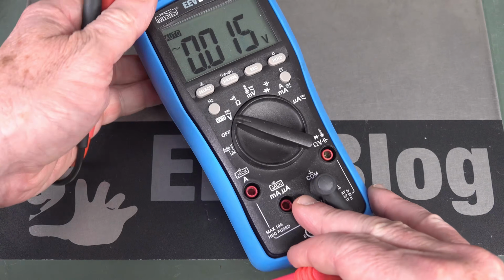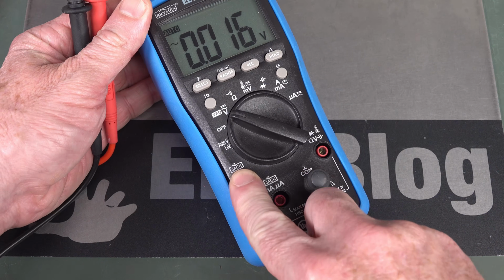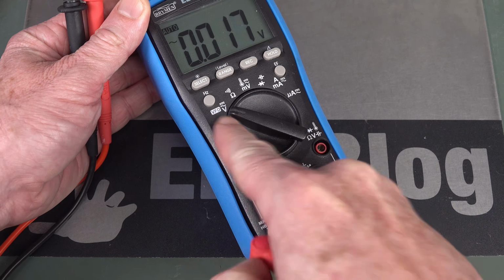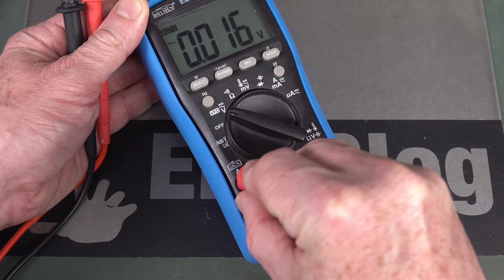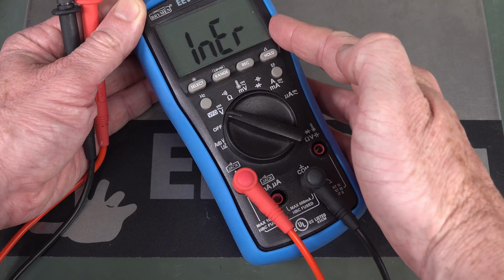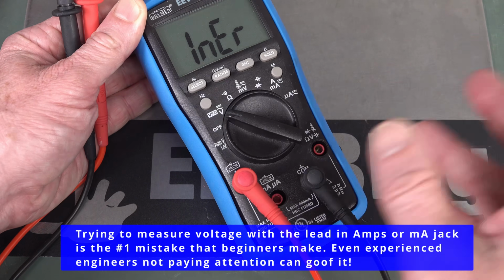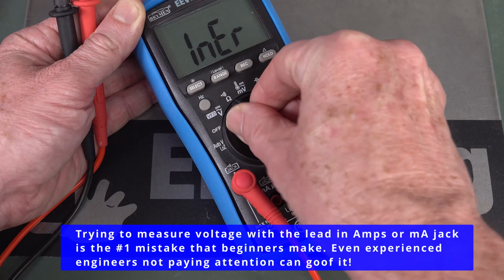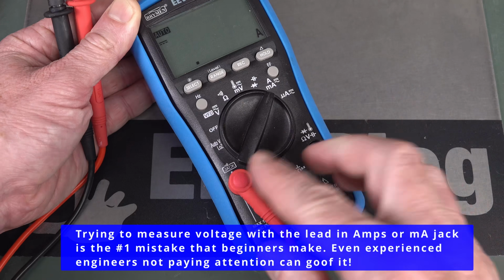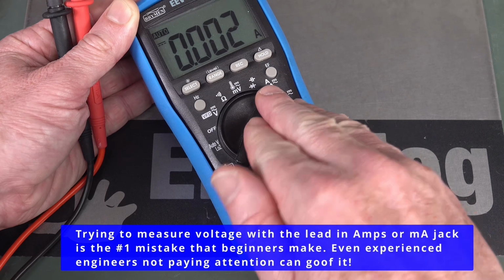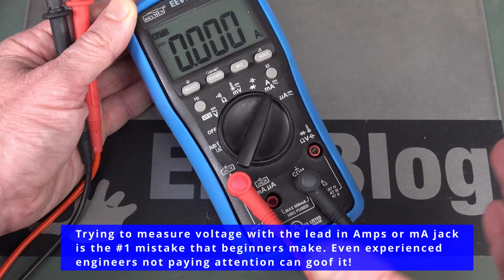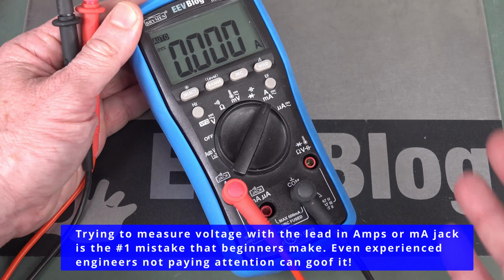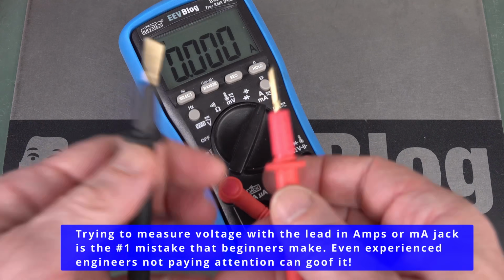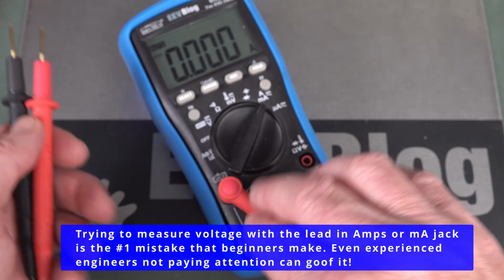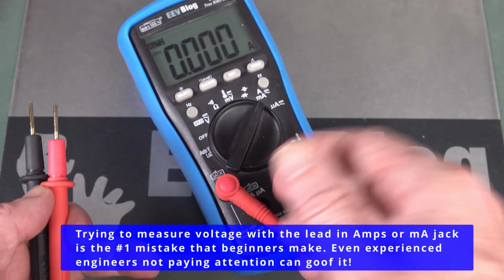This is why some multimeters have what's called an input jack alert. So if I've got it set to voltage, which is incorrect for measuring current, it'll tell me 'insertion error' and beep at me. Not all multimeters have this, but it's a nice function that reminds me as a safety feature that I've got it plugged in here and should select amps. It puts your mind in the correct mindset that this is potentially dangerous if I measure a voltage while in the current measurement range.